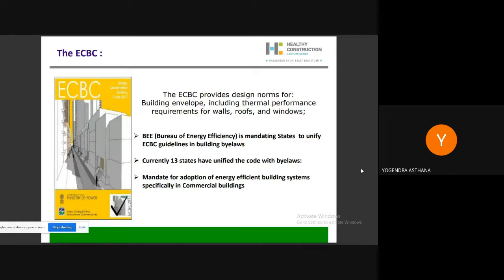So this code says that any building of commercial usage, connected to a load of 100 kilowatt or greater and a contract demand of 120 kVA, has to comply with this ECBC code and should have a reasonably good building envelope, better HVAC facility, conserved lighting, electrical motors and renewable energy.